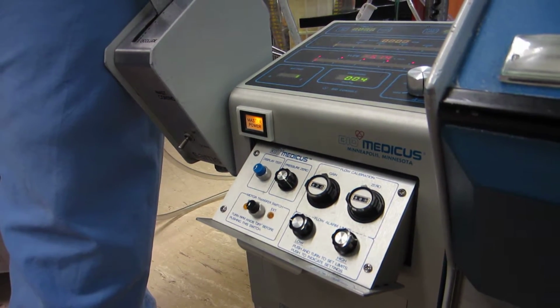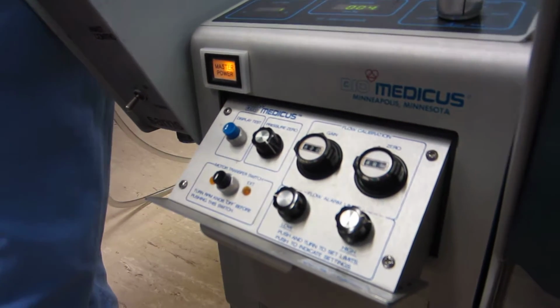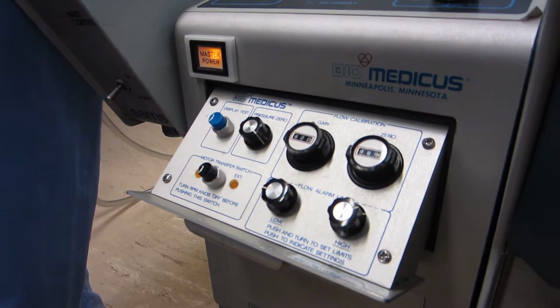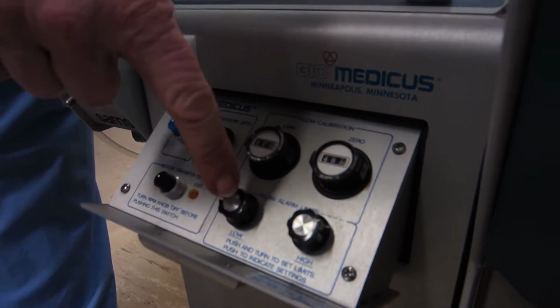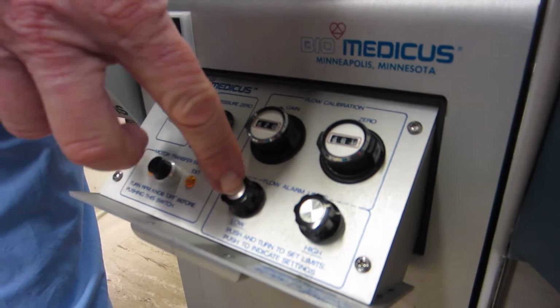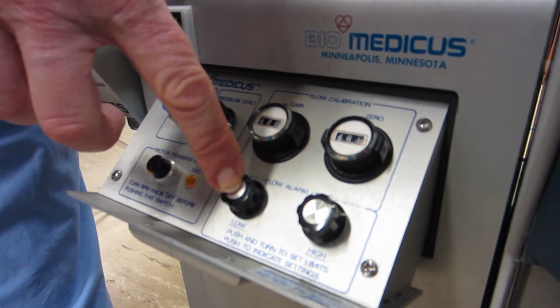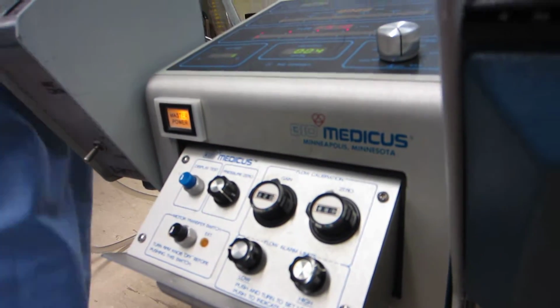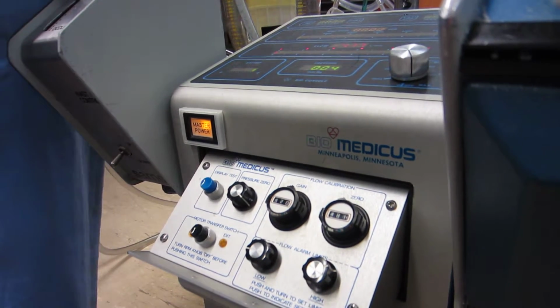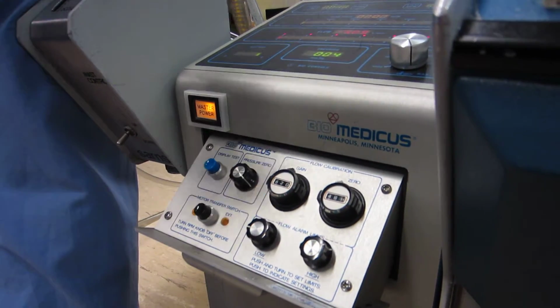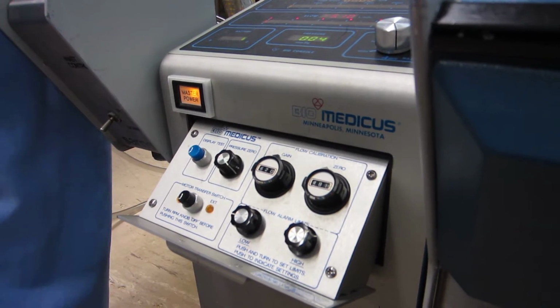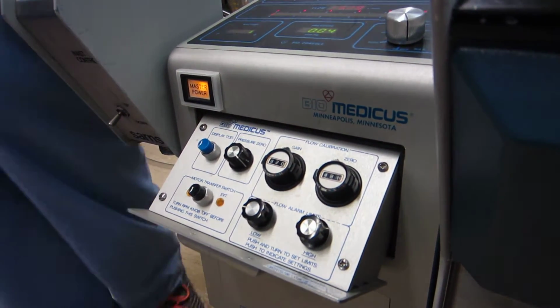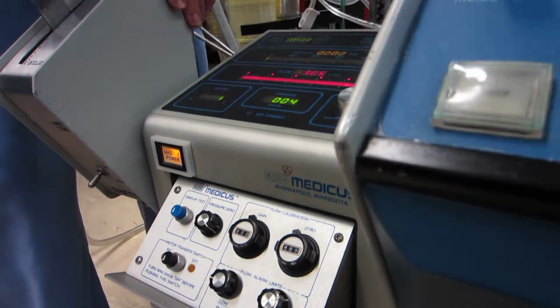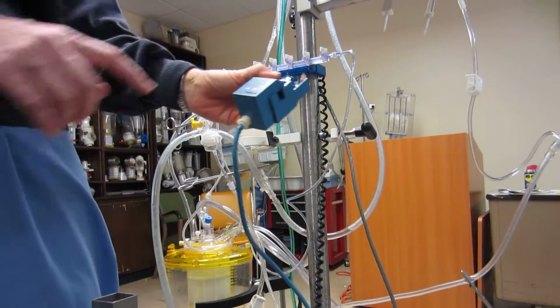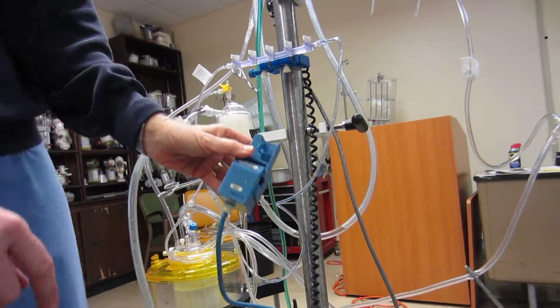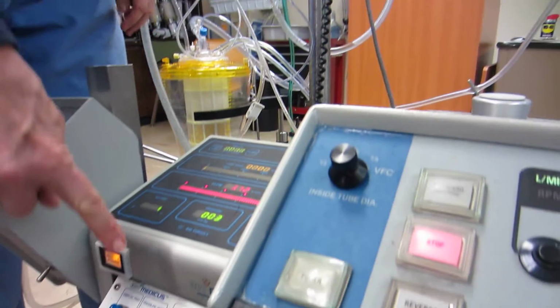Okay, we got low and high level alarms. Do you remember how to set those? So if you depress the button, wherever it lands is what the number is. Okay, you're not going to see anything now because there's no fluid and the flow probe's not attached. So that's why you can't set it. Same thing with high. The difference in the 540 and the other two pumps is you must set a gain with this pump. You get the gain number based on the flow probe. So there's a number on the flow probe, and that's what you have to dial into the gain.